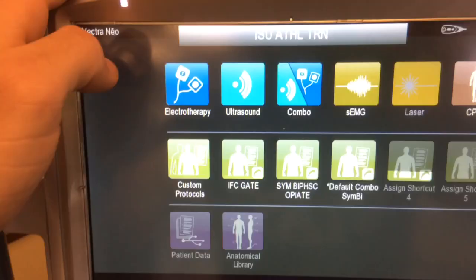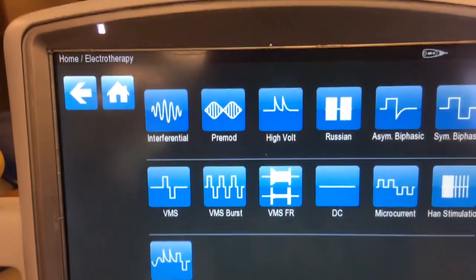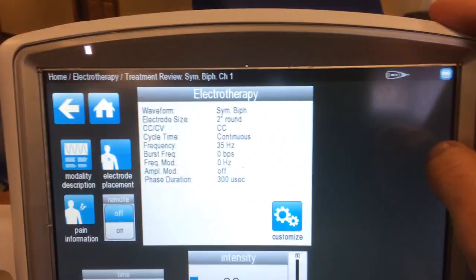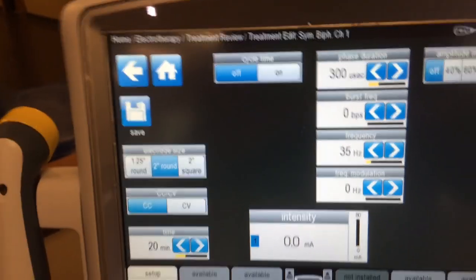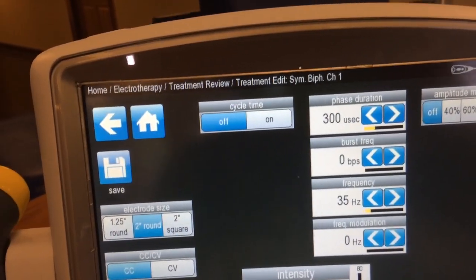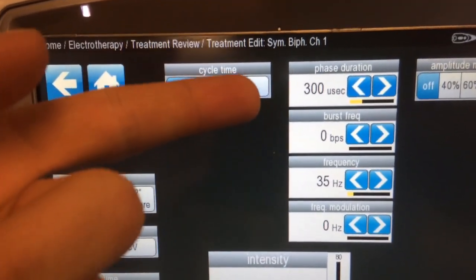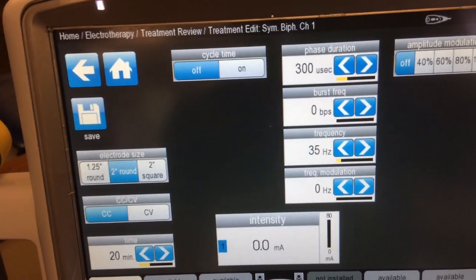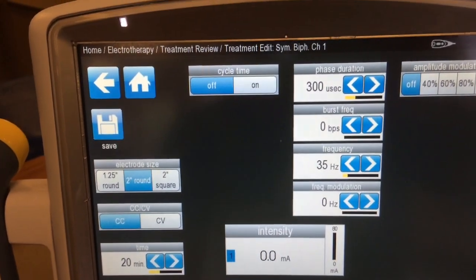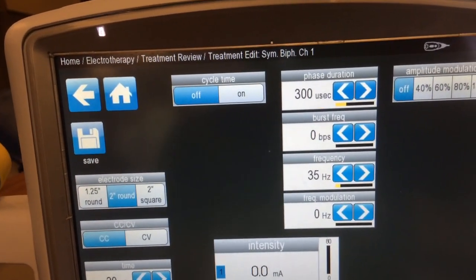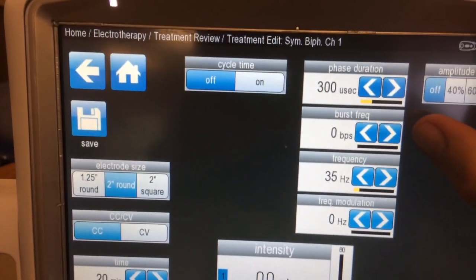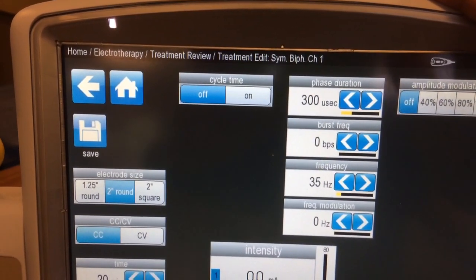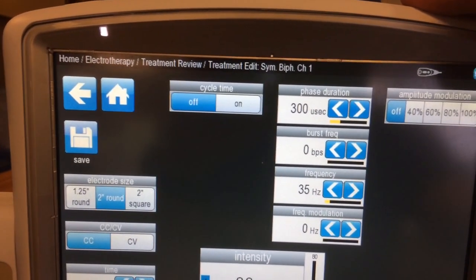Symmetric Biphasic is a versatile waveform because you can actually set the phase duration, essentially creating your own treatment plan rather than following a preset. Phase duration allows lower intensity while still being effective, making treatment more comfortable and more specific to the patient's needs. You can also set burst frequency, so you can configure it like a Russian or muscular re-education treatment using Symmetric Biphasic.